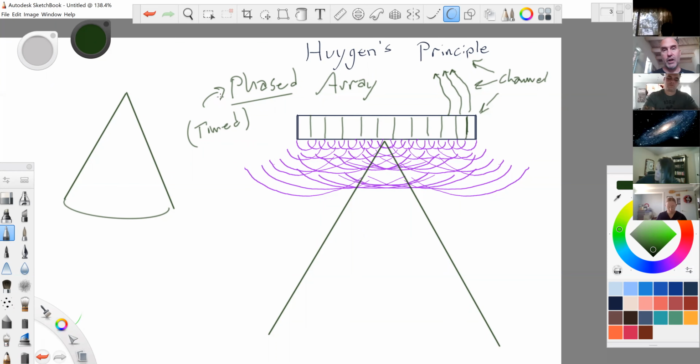The larger elements, our curved element, well, actually our linear transducer as well, are not only phased, but they're sequenced. So you use maybe 10 elements, and then a different 10 elements, and then a different 10 elements. So that's changing every time. On the phased array, every one of these is used every single time.